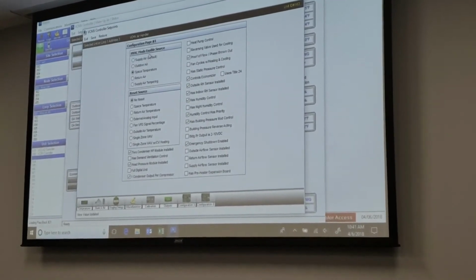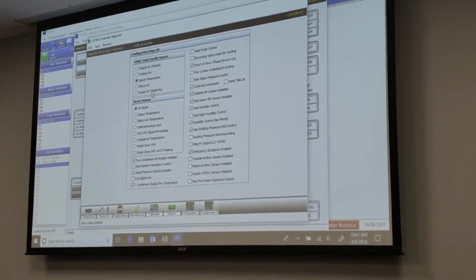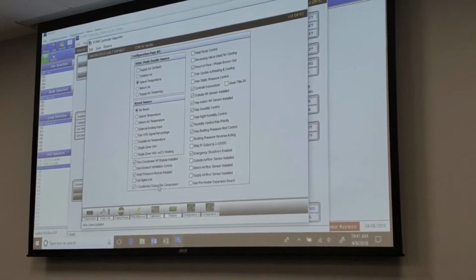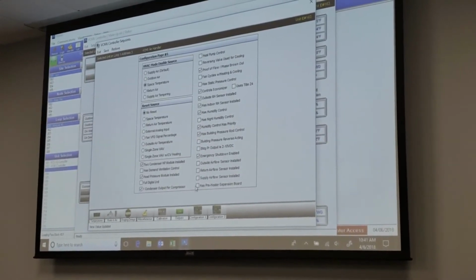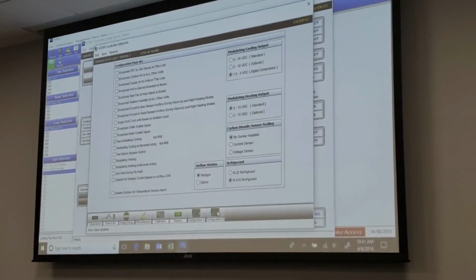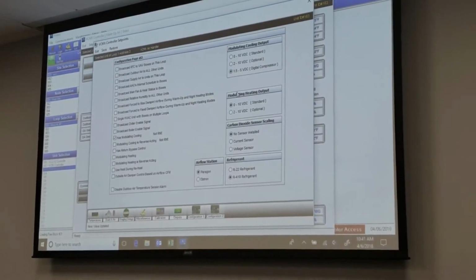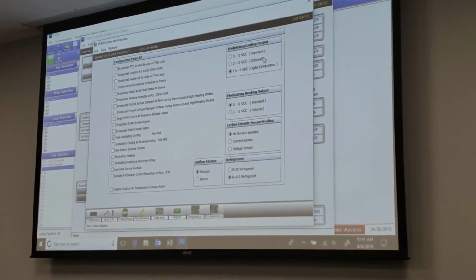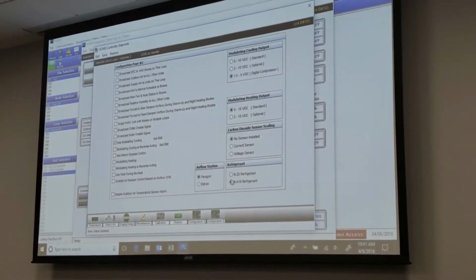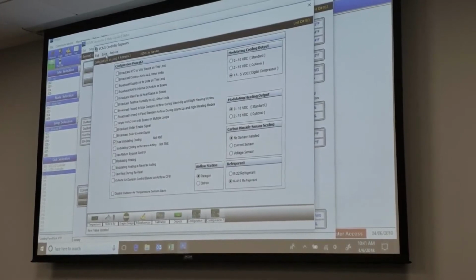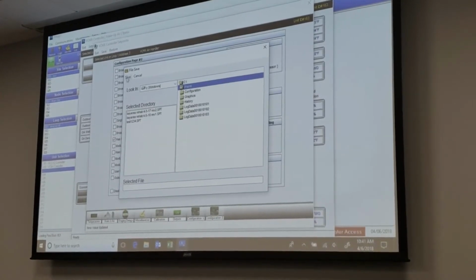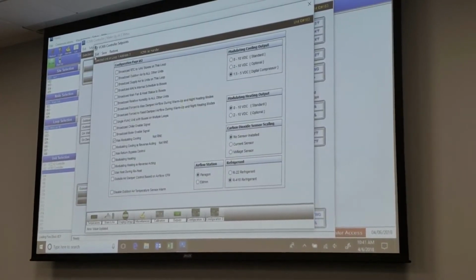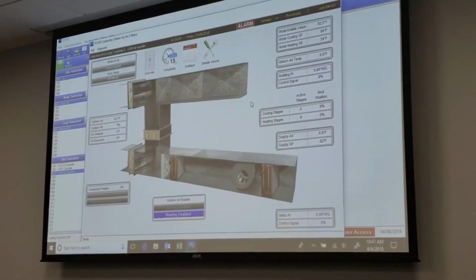Configuration. Makeup air unit. Is it supply air temperature enabled? Space temperature, return air, supply air tempering. Which one do you want? Are we utilizing a reset? Then whatever features you have installed in it, it's just checkbox stuff. 1.5 to 5, digital compressor, 2 to 10, 0 to 10. Once you have all that set, hit save. You can name it whatever you need and go to town with it. That's the cool thing about the Prism software.